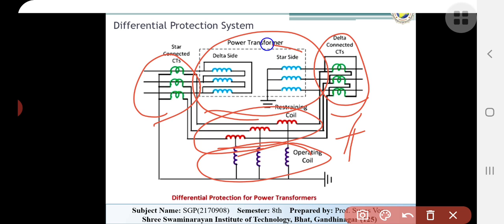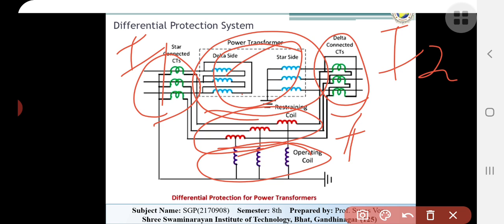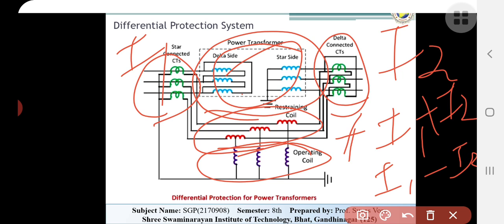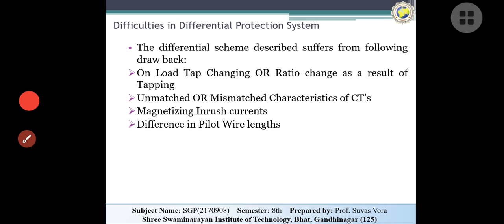If the fault is an internal fault, at that time the input current, if I consider it I1, and the output current is I2. So if I1 plus I2 or I1 minus I2 is not equal to zero, at that time the differential protection system will operate. These are the basic introductions, but here the percentage differential has some difficulties in operating the circuit breakers.